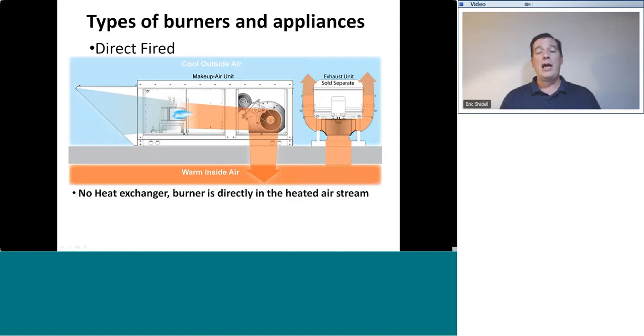In these areas, we have a significant amount of exhaust happening. Take a kitchen, for example. The kitchen has an exhaust hood over the grill or over the fryer, over the griddle, and that is moving smoke and grease and steam and heat from the grill area and exhausting that outdoors. That is a significant volume of air that's being moved, and that air has to be replaced. So we bring in a make-up air unit. It's going to make up for all of the air that's being exhausted. Make-up air units and exhaust fans are linked together so they both operate at the same time, and we get a circular effect. As air is being exhausted, fresh air is being brought in from outdoors.